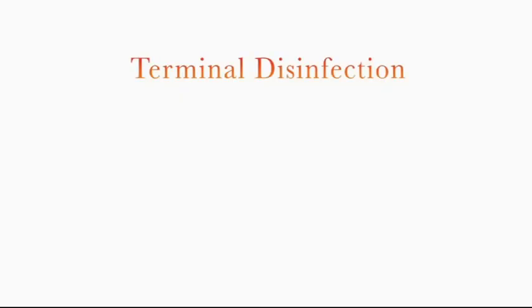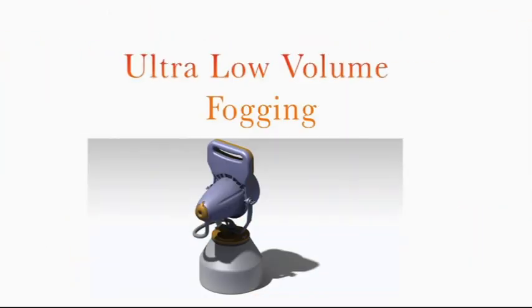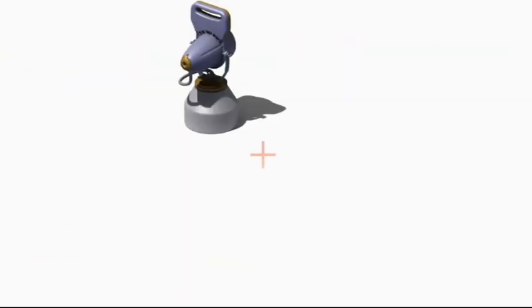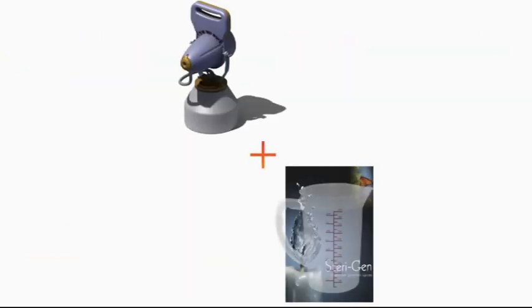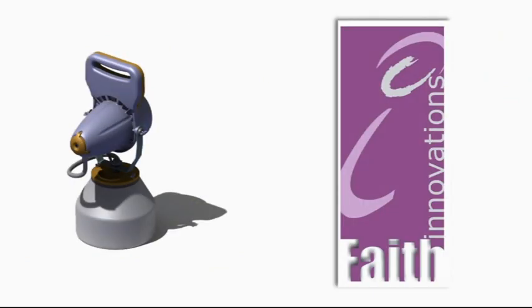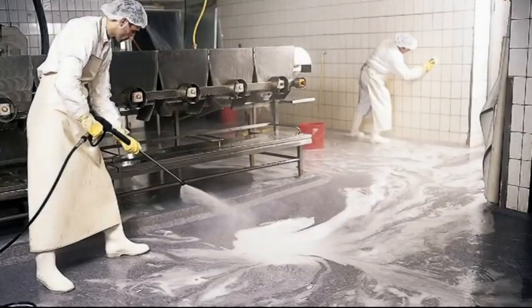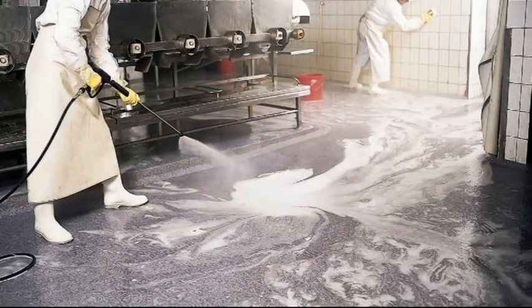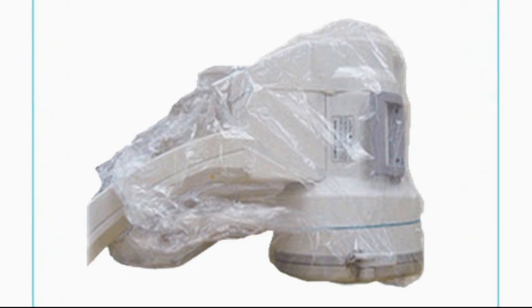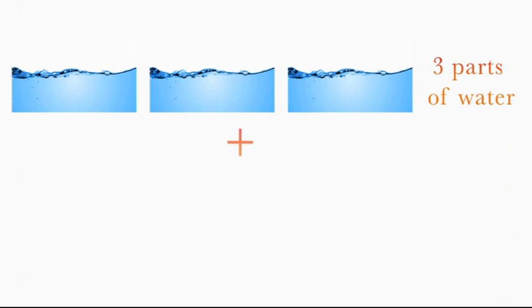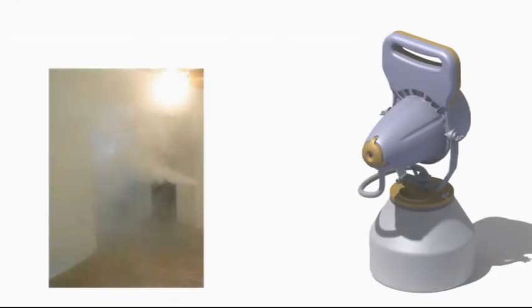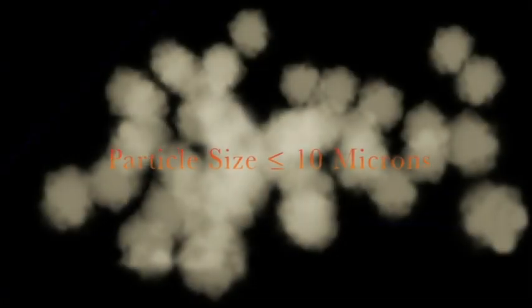For terminal disinfection of operation theaters where ultra low volume fogging is practiced, you need to use a ULV fogger with Sterigen solution. We recommend the use of Sterifog ULV fogger manufactured by Faith Innovations. First of all, clean the room as per the protocol for critical areas using Sterigen solution. Cover the sensitive electromedical equipment with plastic sheets. Fill the ULV fogger tank with 3 parts of water and 1 part Sterigen solution and start the fogger.